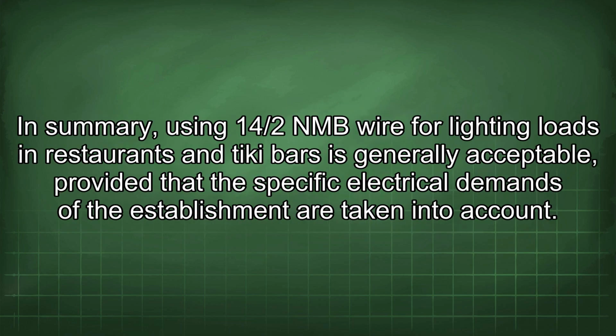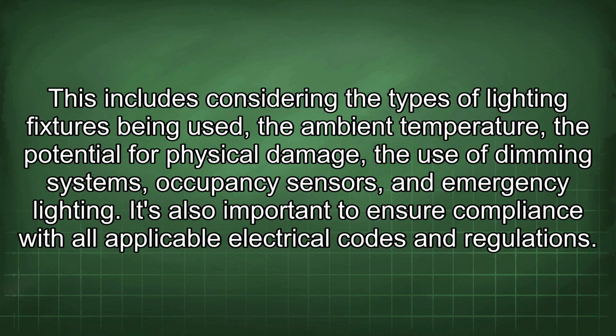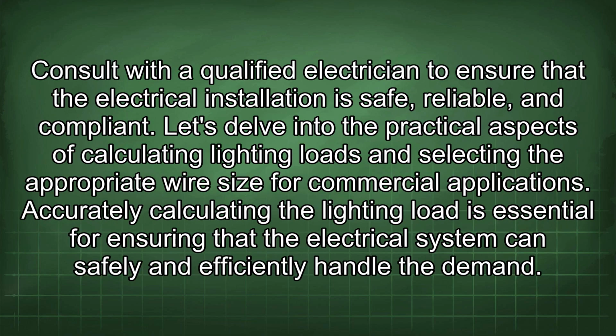In summary, using 14/2 NMB wire for lighting loads in restaurants and tiki bars is generally acceptable, provided that the specific electrical demands of the establishment are taken into account. This includes considering the types of lighting fixtures being used, the ambient temperature, the potential for physical damage, the use of dimming systems, occupancy sensors, and emergency lighting. It's also important to ensure compliance with all applicable electrical codes and regulations. Consult with a qualified electrician to ensure that the electrical installation is safe, reliable, and compliant.